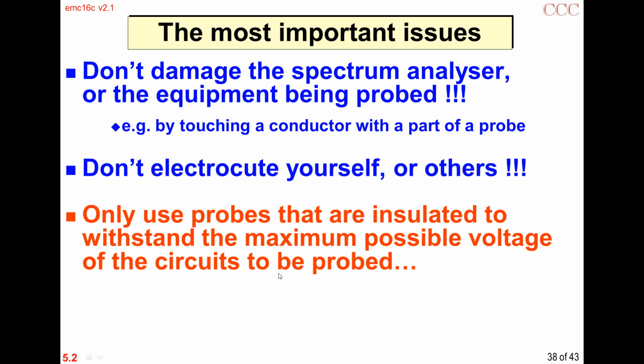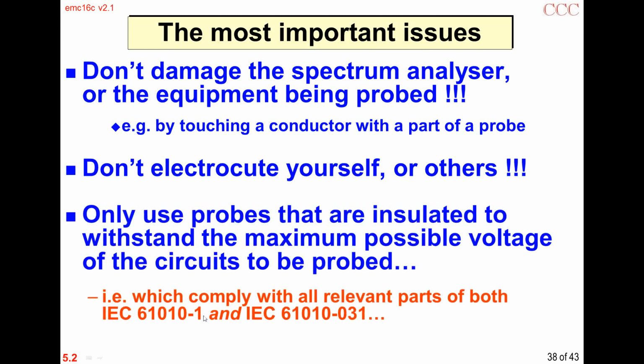It's important to only use probes that are insulated to withstand the maximum possible voltage of the circuits to be probed. On 110, 120, 230 volt mains, the maximum voltage is over 3 kilovolts due to surges. If you want to be really careful, you'd go for 6 kilovolts. There are standards that cover this - standards for insulating probes would be the relevant parts of 61010 Part 1 and 61010-31. In the US, there are UL or ANSI UL versions of these. In other countries, like in Europe, there are EN versions. But these are the basic IEC standards on which the national standards are based.